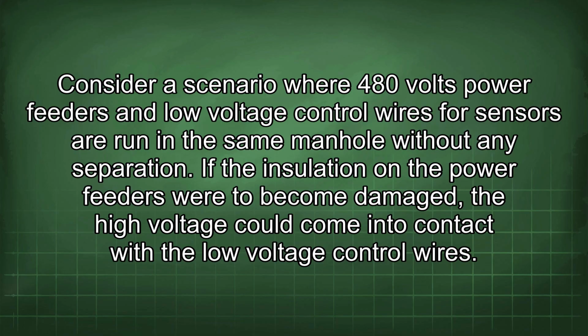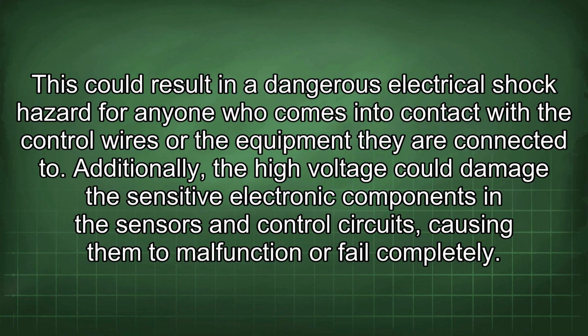Consider a scenario where 480 volts power feeders and low voltage control wires for sensors are run in the same manhole without any separation. If the insulation on the power feeders were to become damaged, the high voltage could come into contact with the low voltage control wires. This could result in a dangerous electrical shock hazard for anyone who comes into contact with the control wires or the equipment they are connected to. Additionally, the high voltage could damage the sensitive electronic components in the sensors and control circuits, causing them to malfunction or fail completely.